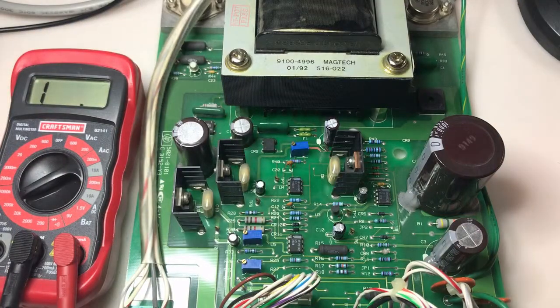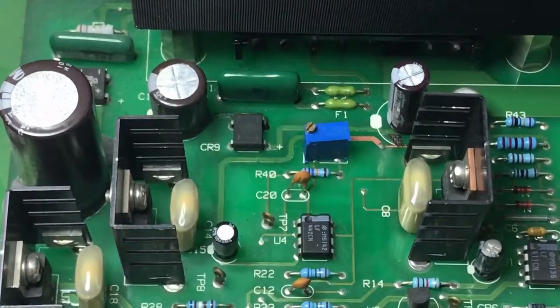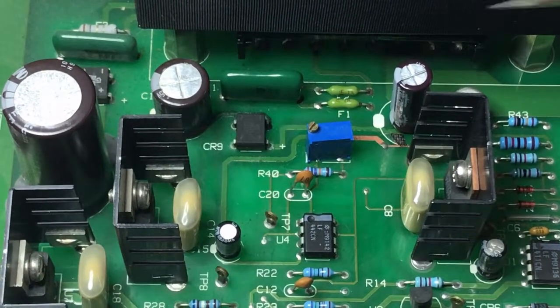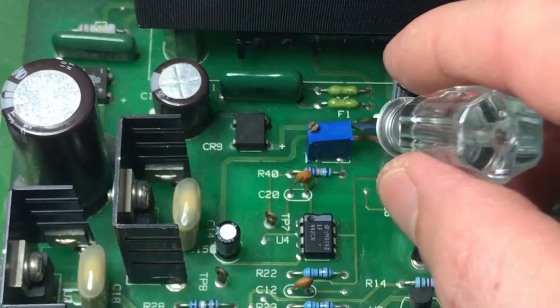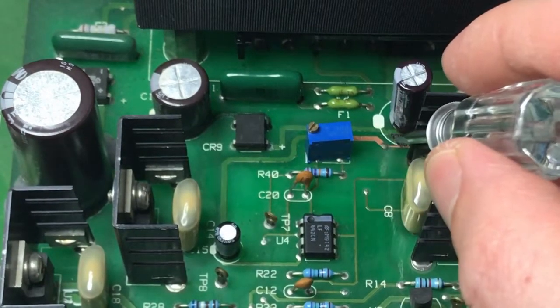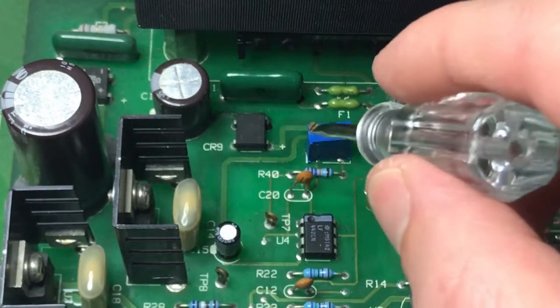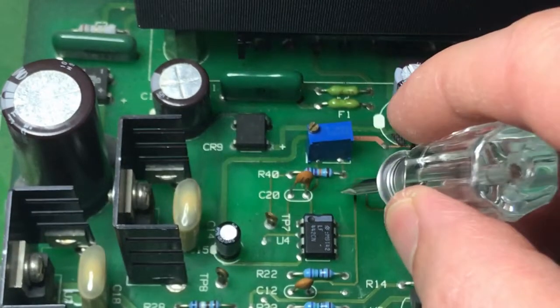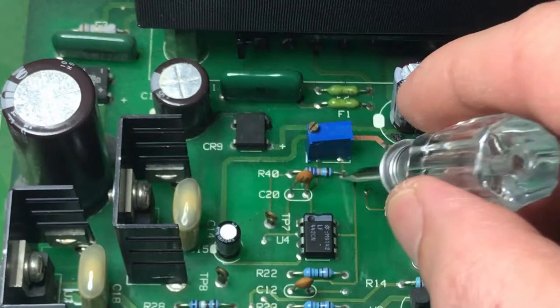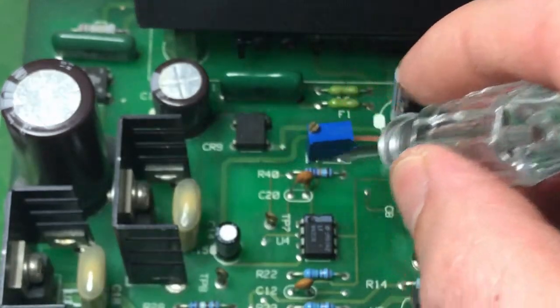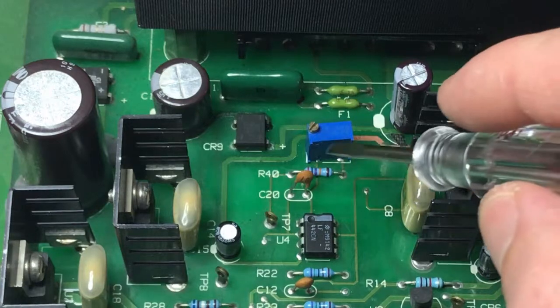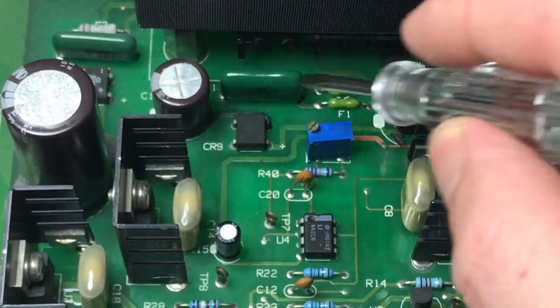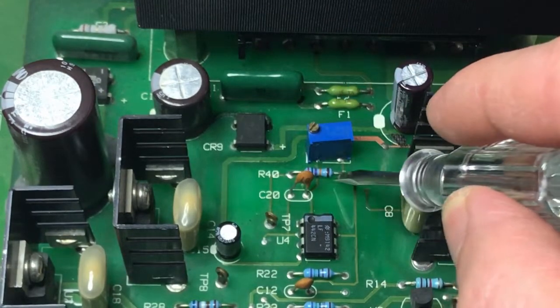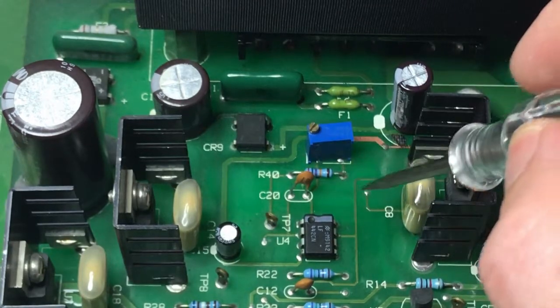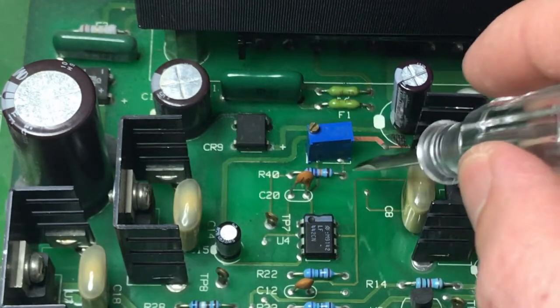The other thing to note, if you look on the board here, so here is the capacitor that I replaced that leaked. Here you can see the bare copper trace where it ate away. And then here's our C20, and here's R40. And some of that electrolyte, although you can't really tell it, there was a very thin layer of film all around this area, including over C20, or R40, excuse me. So potentially it could have got damaged due to that.